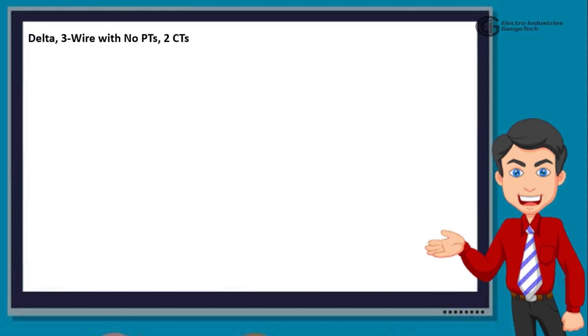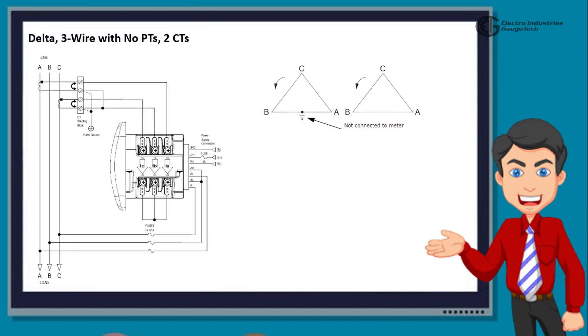The next one is Delta, 3 wire with no PTs, 2 CTs. This diagram shows 3 phase, 3 wire Delta connection with direct voltage. When using this wiring, select 2 CT-Delta from the Shark Meter's front panel display.